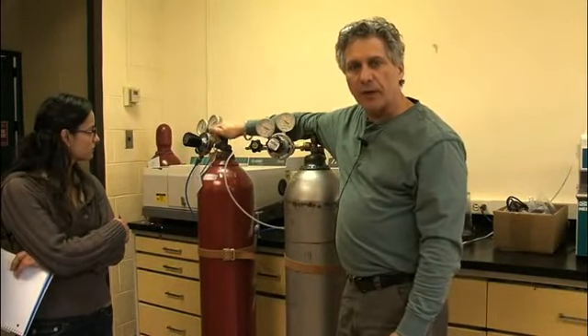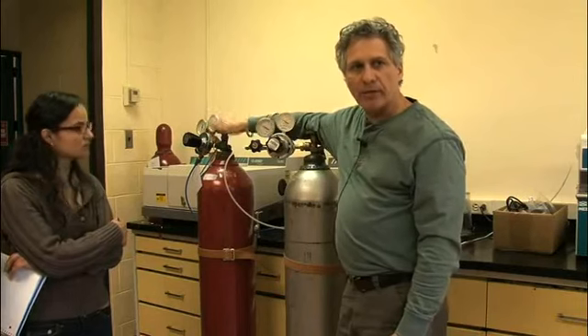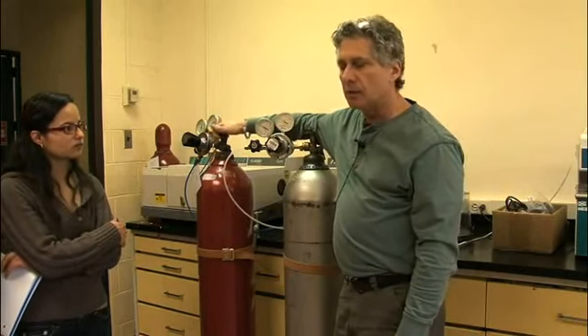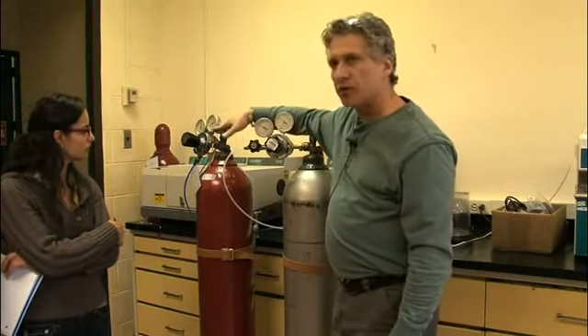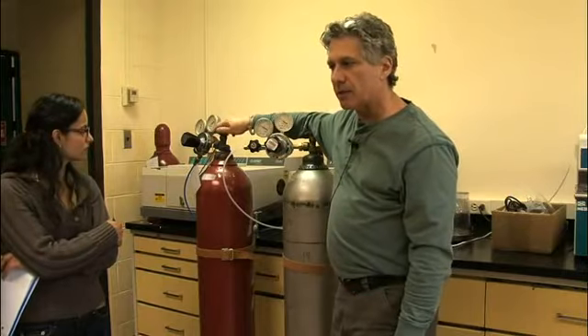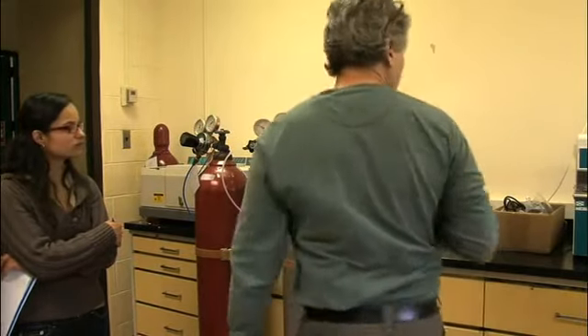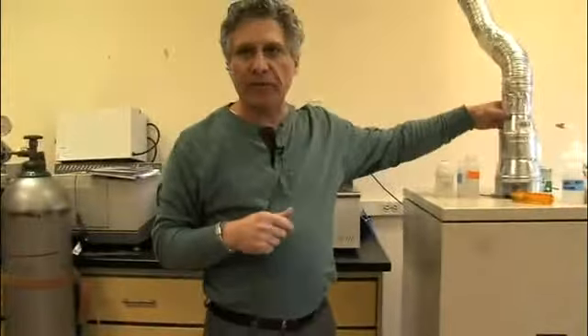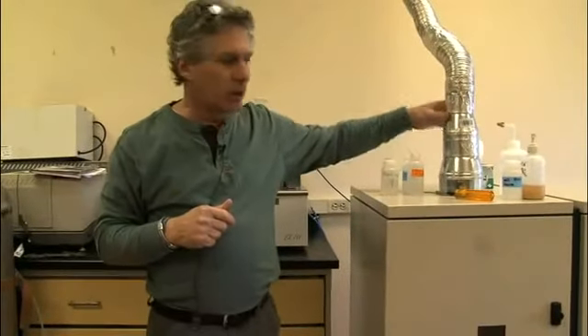And this is used for elements that are going to be analyzed with wavelengths below 190. You need to purge this at least 1 day before you're analyzing those wavelengths. Exhaust should be 100 CFM. I think it's a little low.